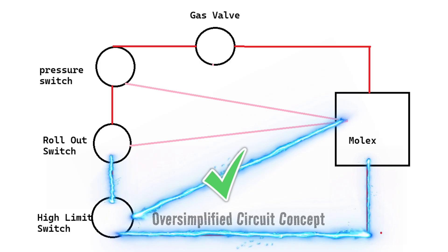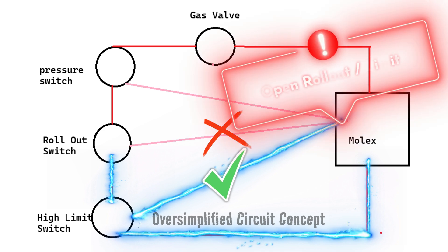Then it goes to the flame rollout switch, but if it doesn't make it back to the Molex plug, the control board can now see that's where it's failing in a circuit, and it can throw out the appropriate error code.